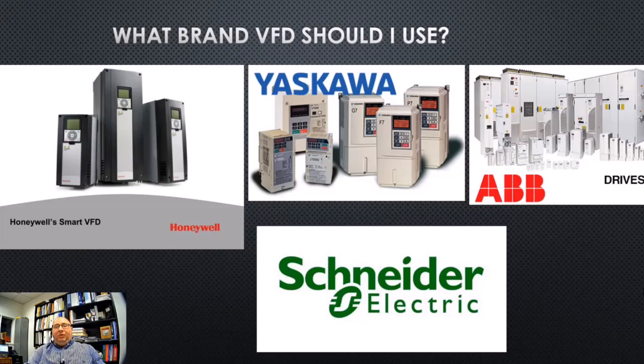manufacturers. I will say out of all 4 of these, the Honeywell is the easiest to use, and the Yaskawa, if I'm saying it right, is probably my least favorite, but it's the most flexible drive and the quality on that is superb because it comes out of Japan. It does some really cool things, such as it could actually heat the windings of your motor if your motor is in a wet environment without actually turning the motor or letting the motor spin. Pretty neat. ABB and Schneider Electric, as you know, are very stable brands in the industry as well, especially when you get into larger machine rooms and air handler rooms.